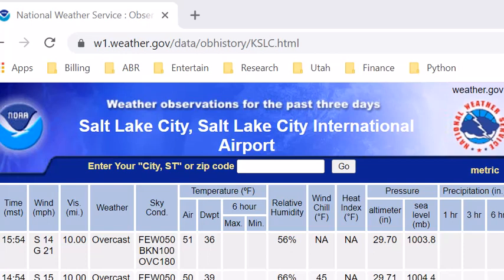So when performing the TG51 temperature and pressure correction, we should not use the pressure value from the airport if our clinic is not at sea level.